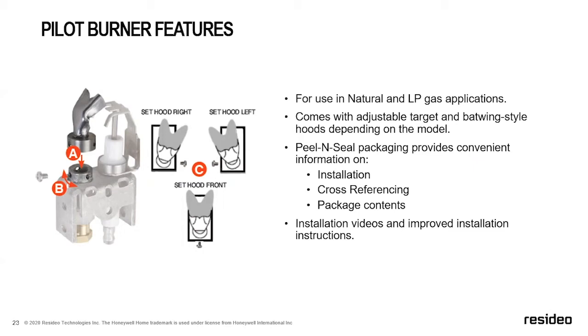The other nice thing about this is inside the box, you also get different orifices depending on what your installation requires, and you also get different break-off fittings, and you also get an offset bracket if you need to mount this in an offset position. There is a chart on the box where you take your existing valve, the existing pilot you're replacing, and match it up, and it tells you the position of the hood, which orifice to use, and whether or not you need the offset bracket. So it makes it real simple. And it's a nice full color display sheet as well, which makes it real nice. There's even a QR code on the box that gives you an installation video that you can take a look at, and it walks you through an installation process for one of these pilots. That's an excellent pilot.